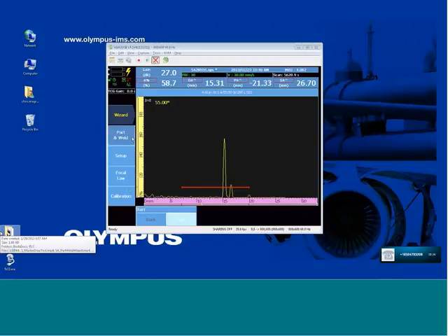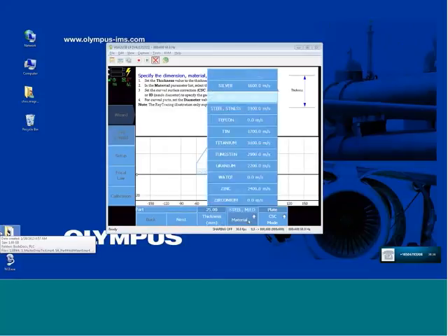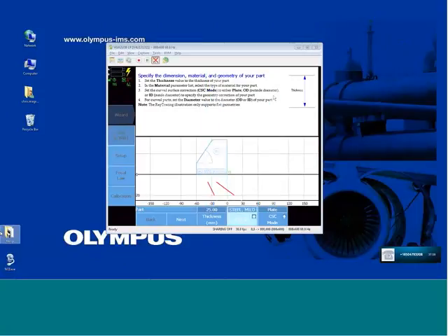The PowerPoint that we just looked at discusses the part and the weld, and it should be a very quick function. Selection of start, enter the material thickness. Again, it has nothing to do with the component's beam formation. It's just the skip lines. We will select velocity from the database. And we will select plate for piping girth welds or for plate geometry, meaning that the ID and OD surface are parallel and not curved.